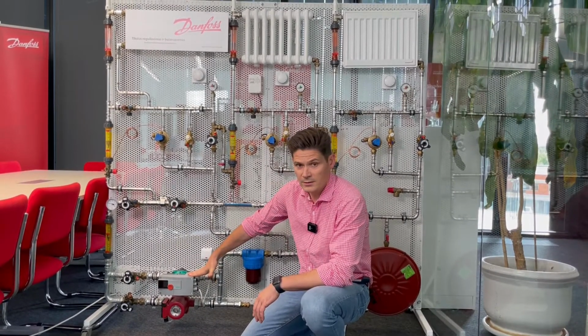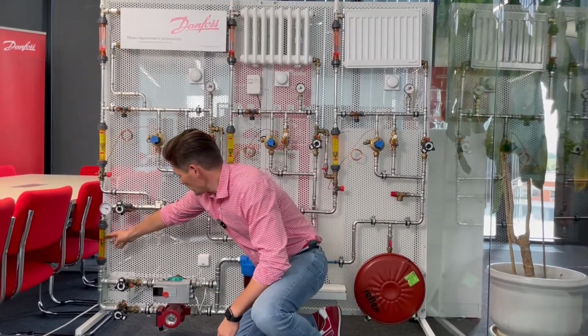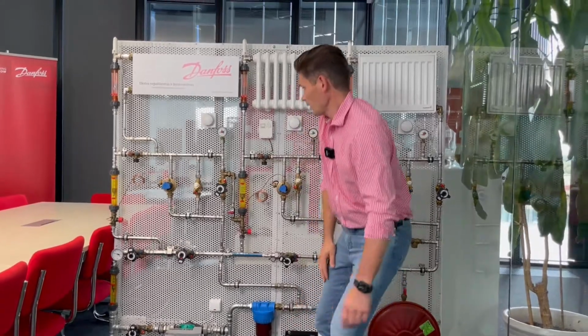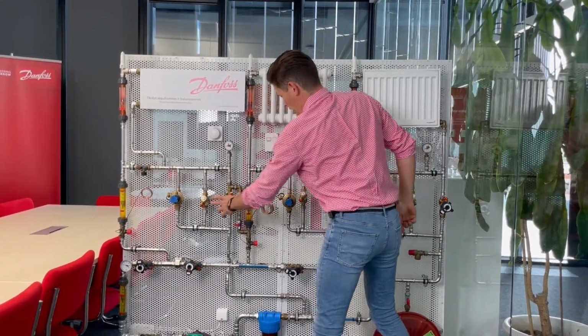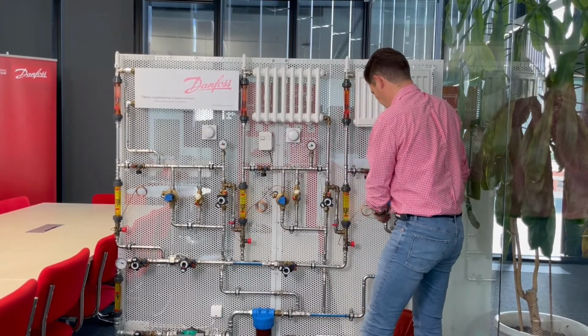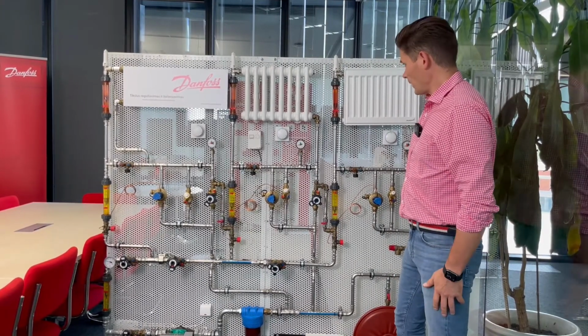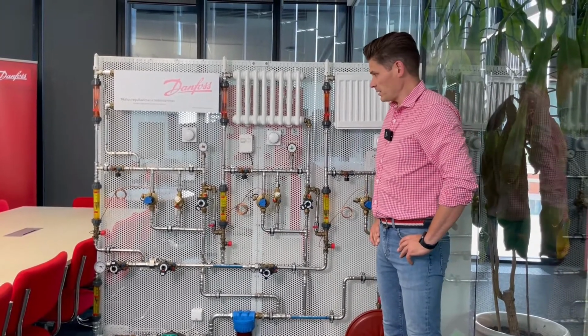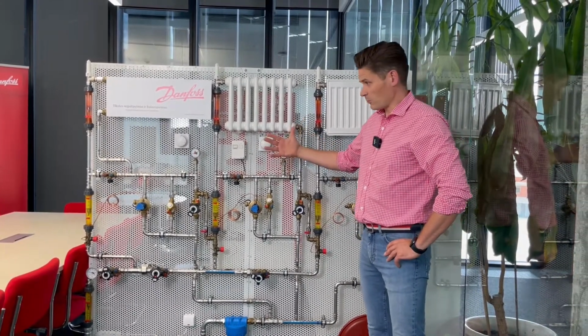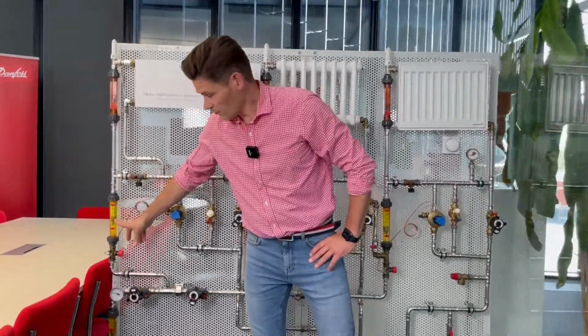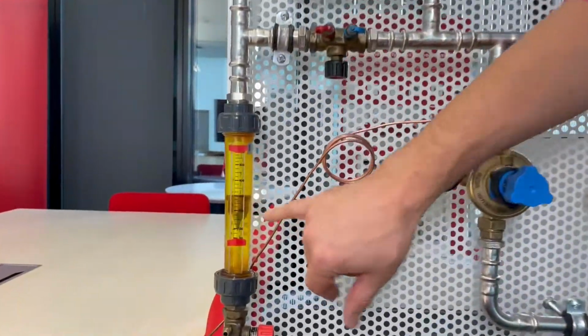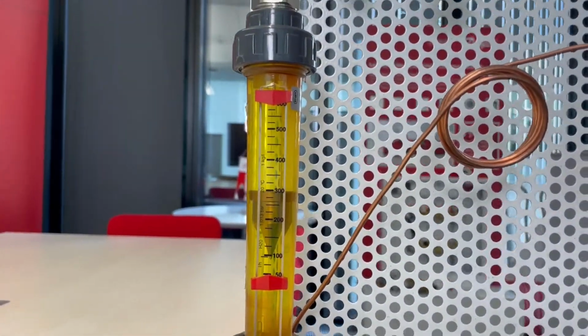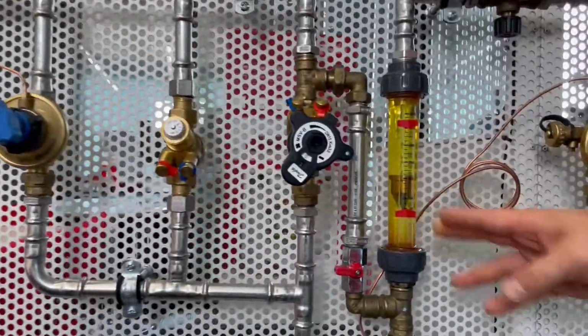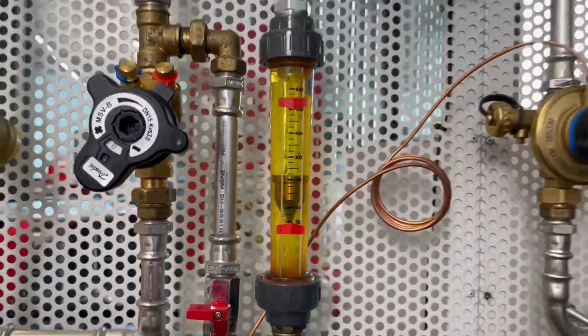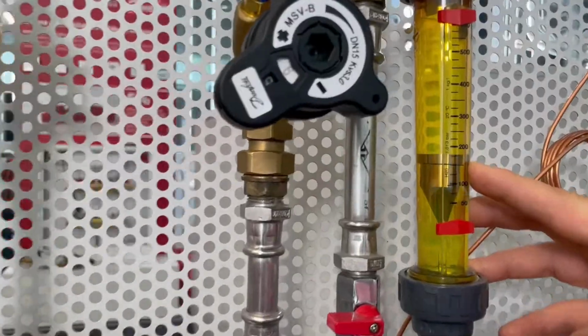We have 2 pumps, one is a three speed pump, the green one is automatic with a frequency converter. And here is the supply pipe, it goes to the first riser. So all automatic balancing valves now are closed, the manual one is fully open, closed, closed, fully open, closed, closed, and this one is fully open. As you might predict, the first riser gets maximum flow, and here we have a flow meter and can check the flow at the first riser. So at the first riser we have 300 liters. Second riser is here, we have 220 liters. And the third, the last riser, we have 180 liters.